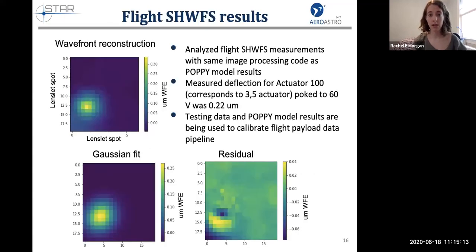Here's an example of applying the Shack-Hartmann wavefront sensor wavefront reconstruction code to data from the flight payload. Here is a wavefront reconstruction, a Gaussian fit, and a residual measurement for actuator number 100, corresponding to the 3,5 position, poked to 60 volts. In this case, we measured a deflection of 0.22 micron.